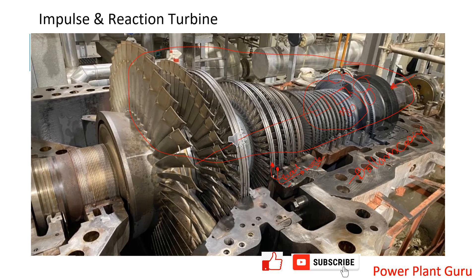Nozzles are fixed in the top and bottom casing while the buckets are mounted on the rotor. Steam flows from the high-pressure, high-temperature end initially — there is high energy in the steam, so smaller blades can extract that energy. As the steam pressure and temperature drop, the volume increases, and to extract the right amount of energy from the steam the surface area of the blades has to increase.